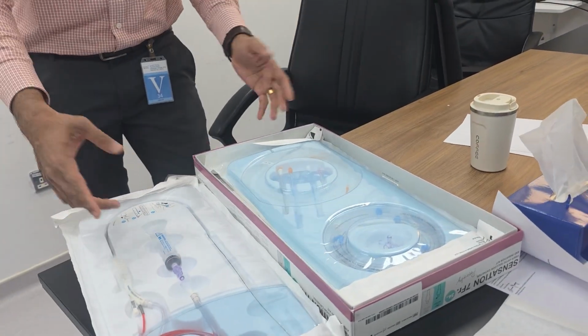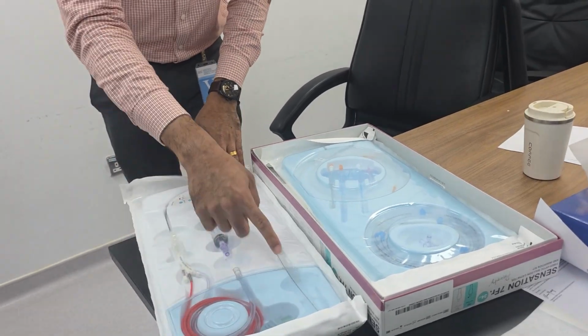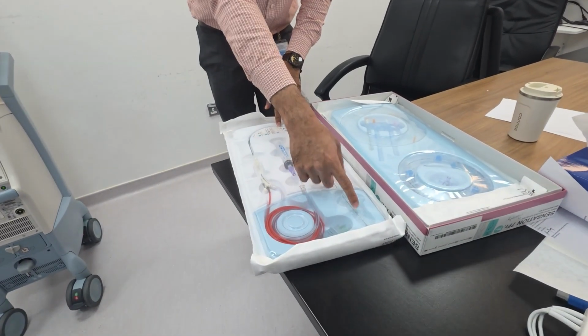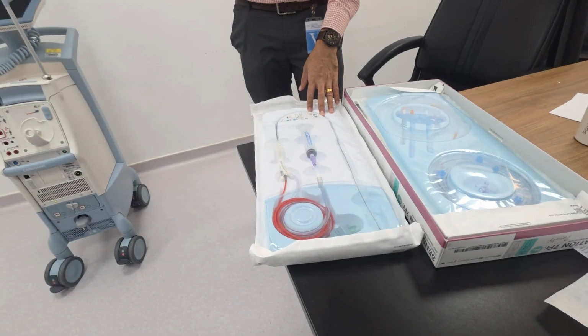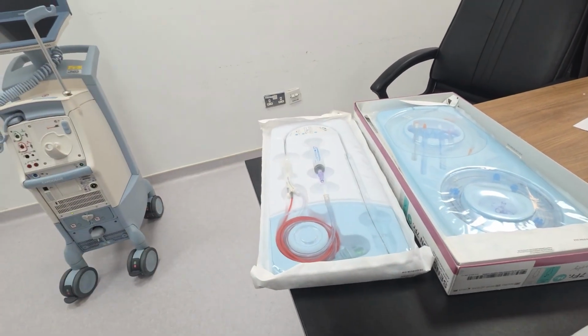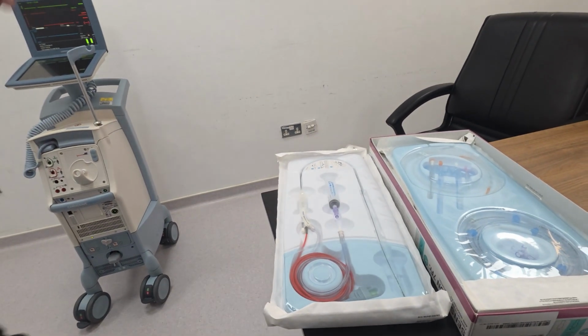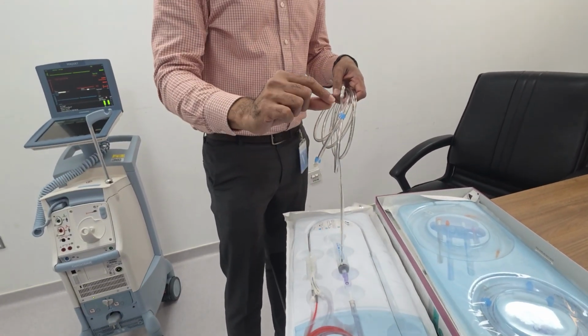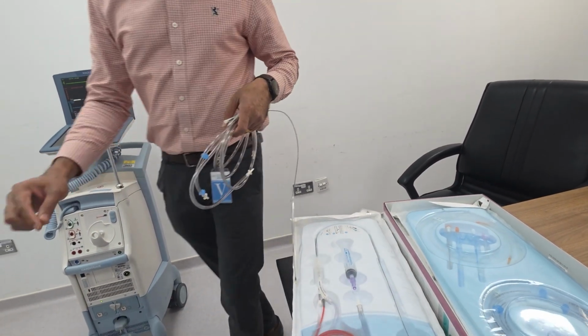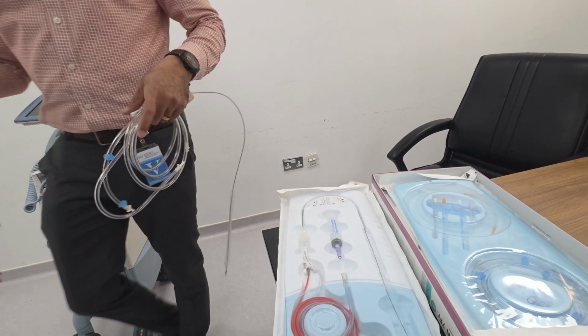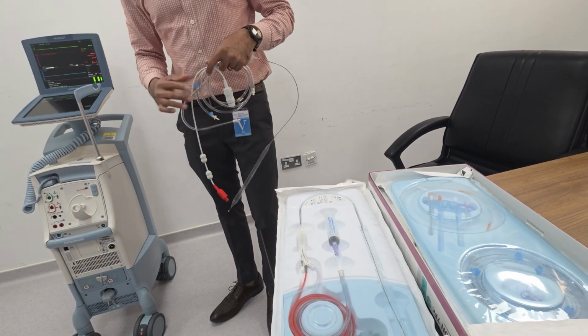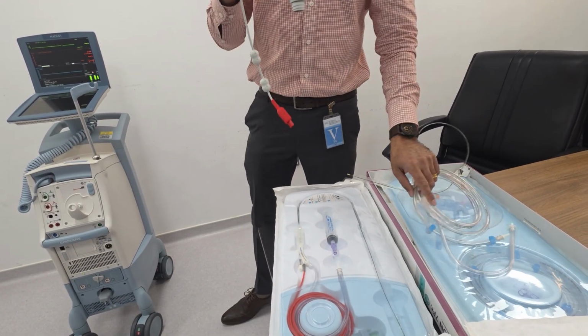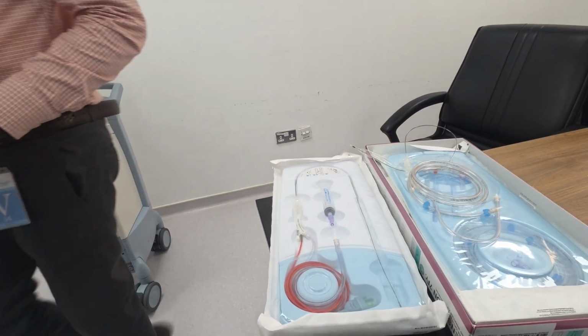The difference is that with fiber, you have an extra orange wire. It has a pressure sensor on the tip of the balloon. This can measure the pressure inside the aorta. So if we are using the traditional normal balloon, it doesn't have the orange wire, so you have to connect the pressure transducer here. In that case, I told you, you need to use this connection with the pressure transducer. But unfortunately, no, it's the same connection, not big differences.